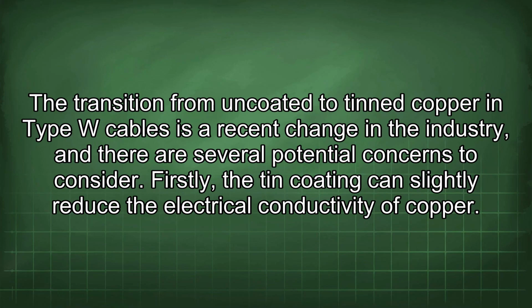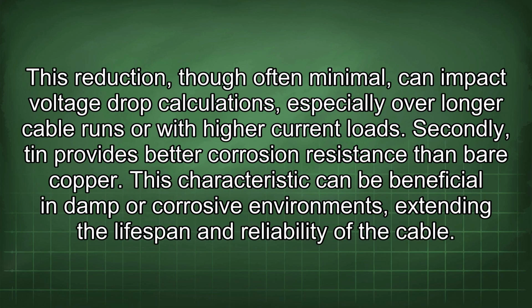The transition from uncoated to tinned copper in Type W cables is a recent change in the industry, and there are several potential concerns to consider. Firstly, the tin coating can slightly reduce the electrical conductivity of copper. This reduction, though often minimal, can impact voltage drop calculations, especially over longer cable runs or with higher current loads. Secondly, tin provides better corrosion resistance than bare copper. This characteristic can be beneficial in damp or corrosive environments, extending the lifespan and reliability of the cable.